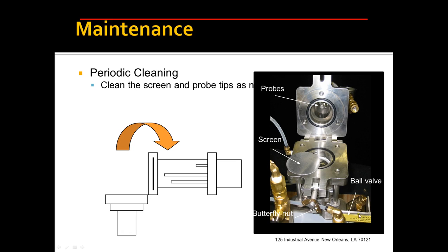The ball valve is right down here. Here's the wing nut. There's the screen, and you can see one of the probe tips, and we provide you with a little bottle brush that you can use to keep all those things clean. Of course, when you've got it open, you want to clean the screen and inspect the gaskets, but that's basically the alpha and omega of cleaning. It will probably take your team longer to walk out to the instrument than it will actually take to clean the instrument. Very straightforward to do. And there is a video on YouTube, by the way, of yours truly performing the cleaning methodology, and I encourage you to look at it.